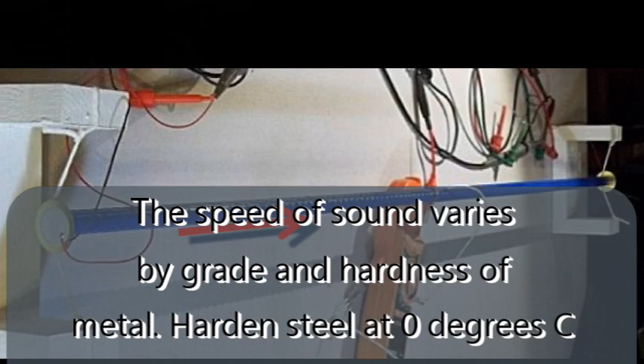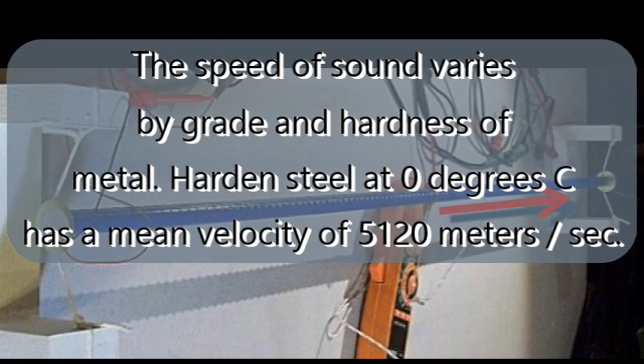But they are multiple echoes, because the frequency and corresponding wavelength are significantly slower. Multiple waves enter the bar before the first wave reaches the end receiver transducer. The professor will show this later. This velocity, or 5,084 meters per second, is very close to other documented experiments into the speed of sound through iron, which in general states 5,120 meters as the mean velocity.